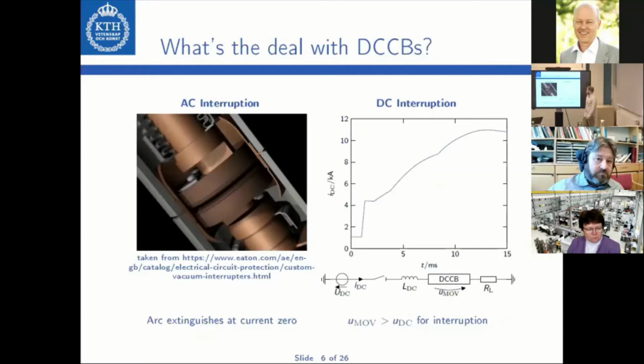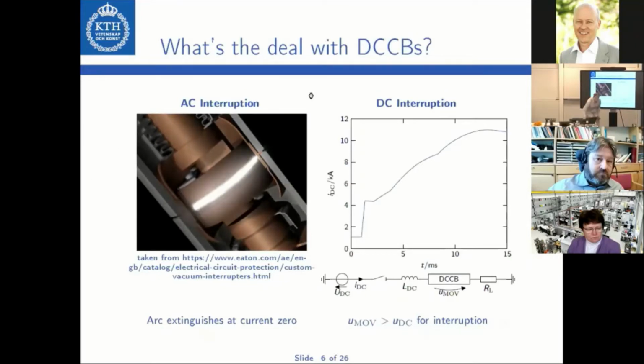One question is, what's the deal with DC circuit breakers in the first place? Why are they so complicated? In an AC system, the fault current has a natural current zero crossing. The AC circuit breaker consists of two contacts that are opened, drawing an arc. The contacts open and the arc keeps on burning. At some point, the natural current zero crossing occurs and the arc in the circuit breaker extinguishes. The AC circuit breaker then has isolated the AC fault.